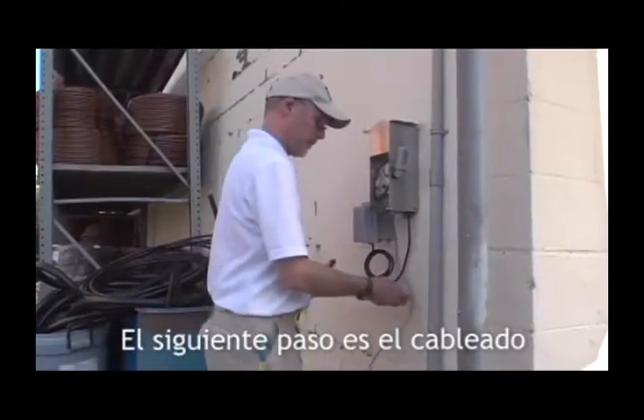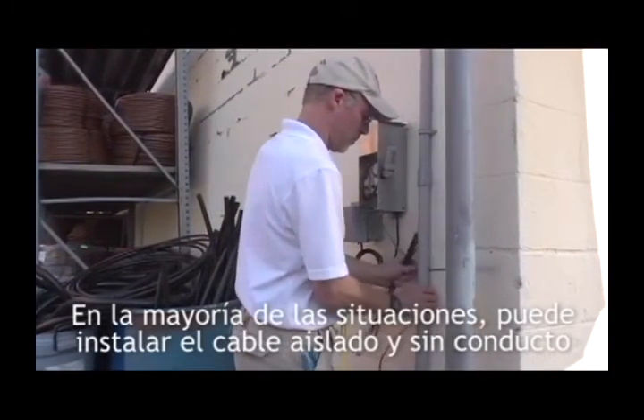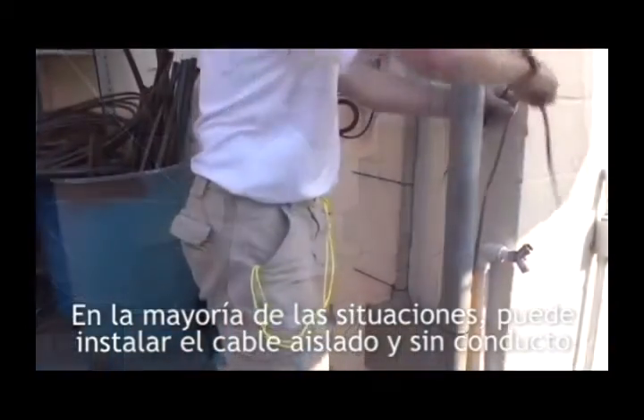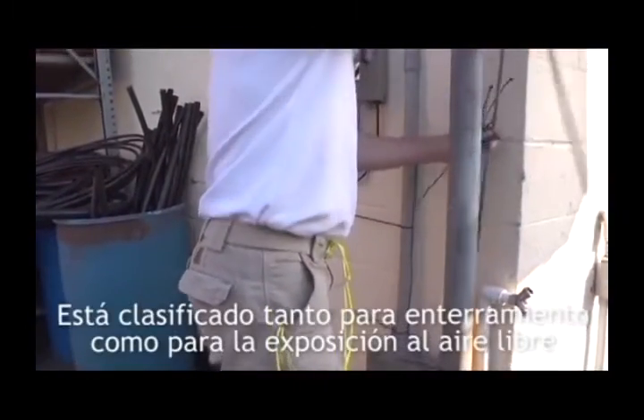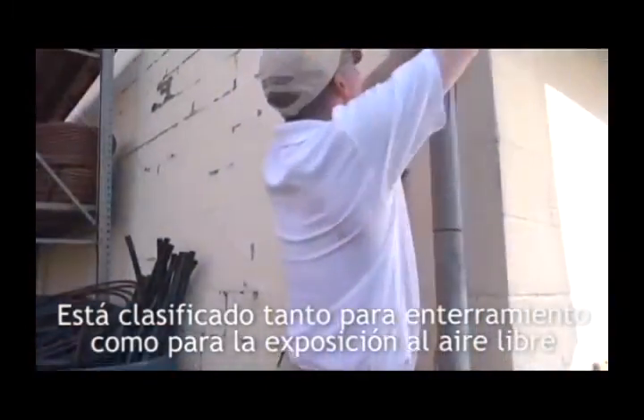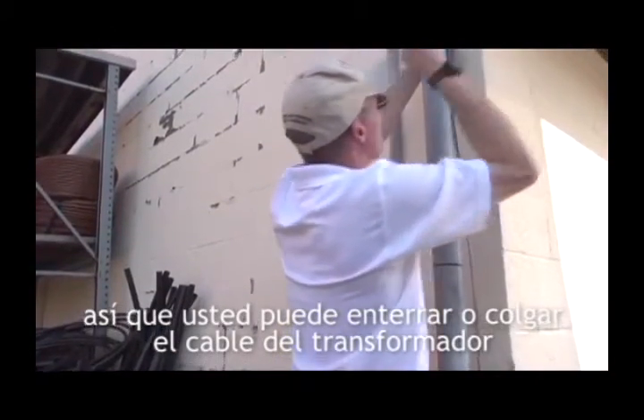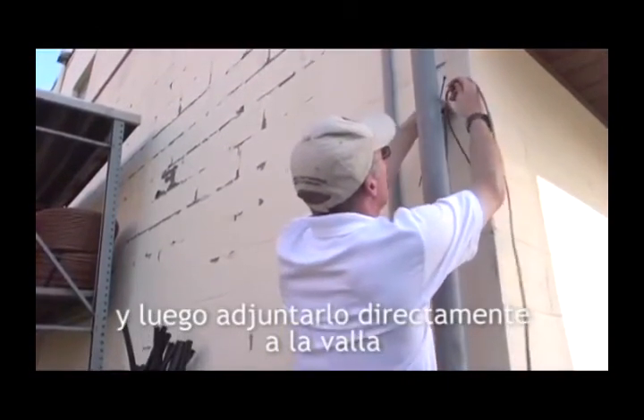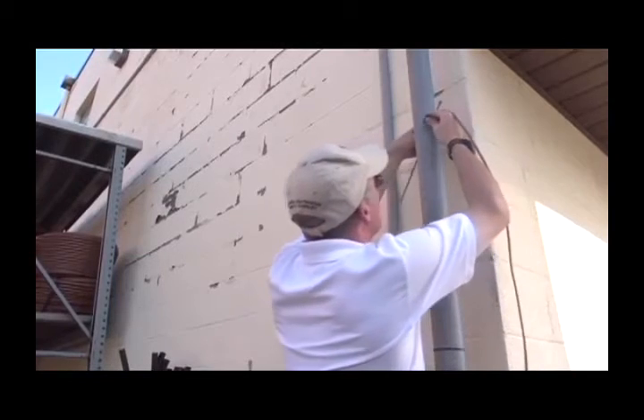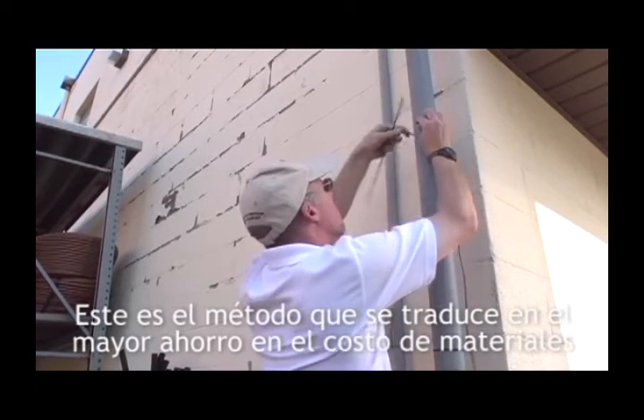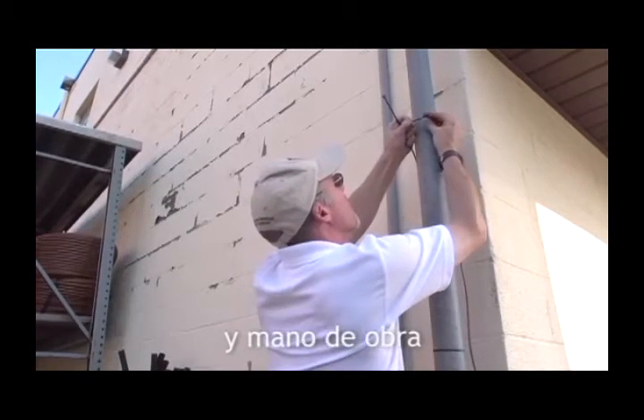The next step is wiring. In most situations, you can run the insulated wire without conduit. It's rated for both burial and outdoor exposure, so you can bury or hang the wire from the transformer and then attach it directly to the fence. This is the method that results in the greatest savings in material and labor cost.